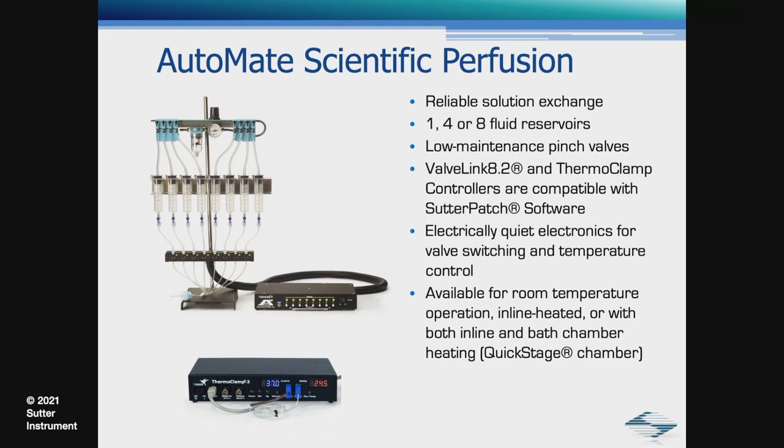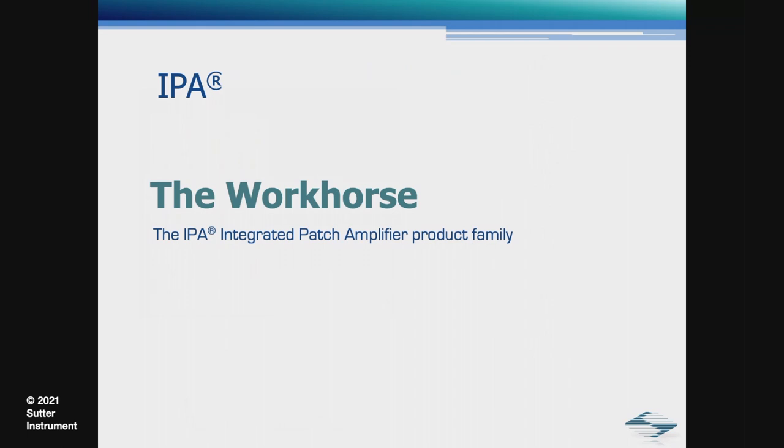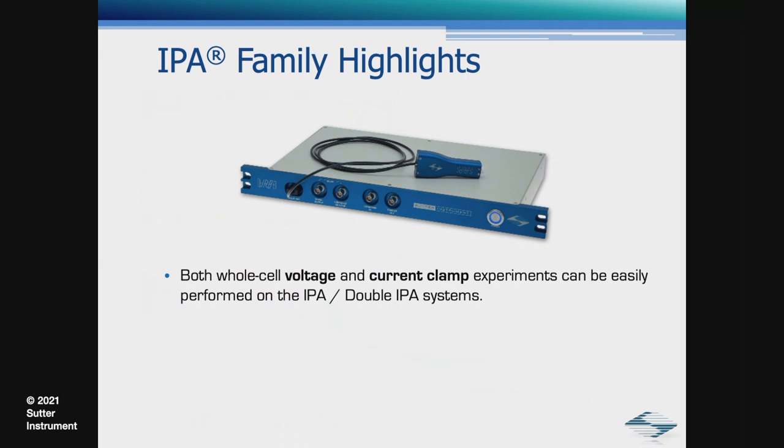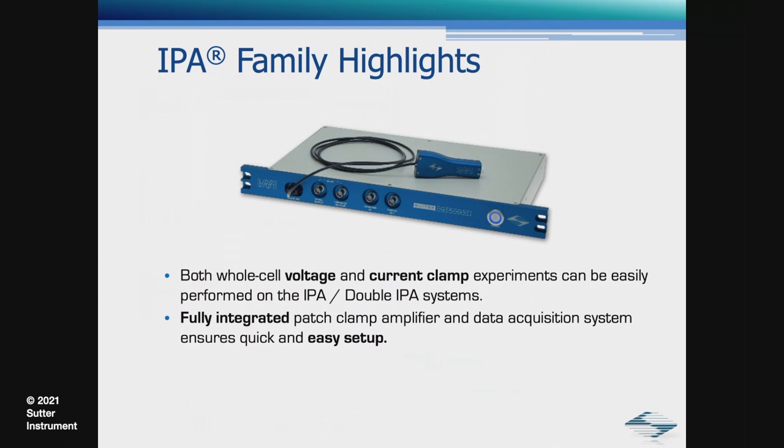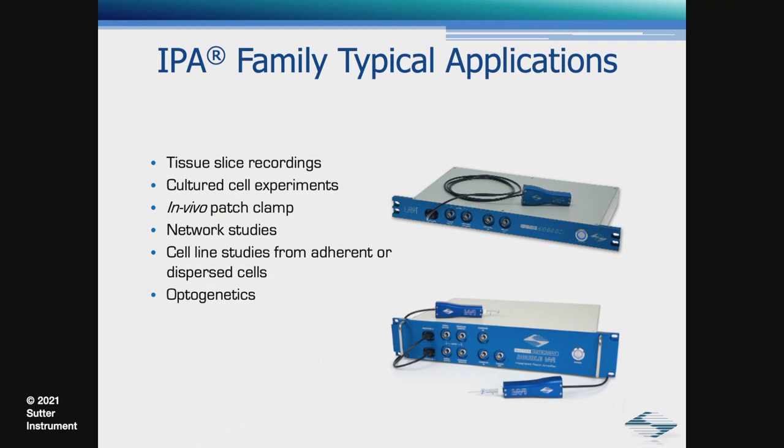The final piece of the puzzle is our amplifier system. Sutter has a couple of options. The feature set of the IPA will meet the requirements for the bulk of our customers. The IPA is available in either a single head stage or dual head stage configuration. Typical highlights include whole cell voltage and current clamp experiments, fully integrated patch clamp amplifier with data acquisition system, and includes the Sutter Patch data acquisition software. The IPA is well-suited for tissue slice recordings, cultured cell experiments, optogenetics, to name a few.